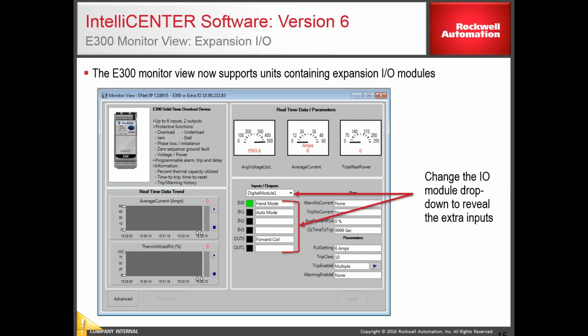So with the E300, the new thing that we've added, and with E300 it comes standard with, I think there's 6 digital inputs, there's a couple outputs, but there's also some expansion I/O modules that you can add to the E300. So if you want to bring in some discrete inputs to that device, you can add expansion modules. Now we have those available as a monitor to view within IntelliCENTER software. So if you've got 2 or 3 modules, you select the module you want to look at, then you get status on those inputs on those specific modules. Okay, so that's something new that's been added to the IntelliCENTER software.